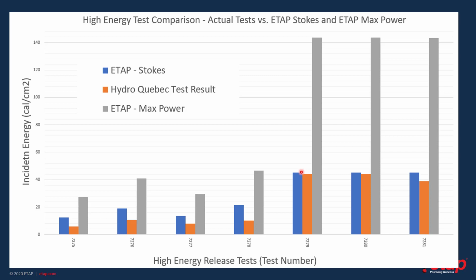For that adjustment, I would like you to consult with ETAP technical support or myself so I can explain how we need to adjust the methods or apply the options so that we can get this kind of accuracy in the simulation. We can also see that the prediction of the maximum power method is approximately 140 calories per centimeter square, when the actual measured incident energy is only 40 calories per centimeter square.